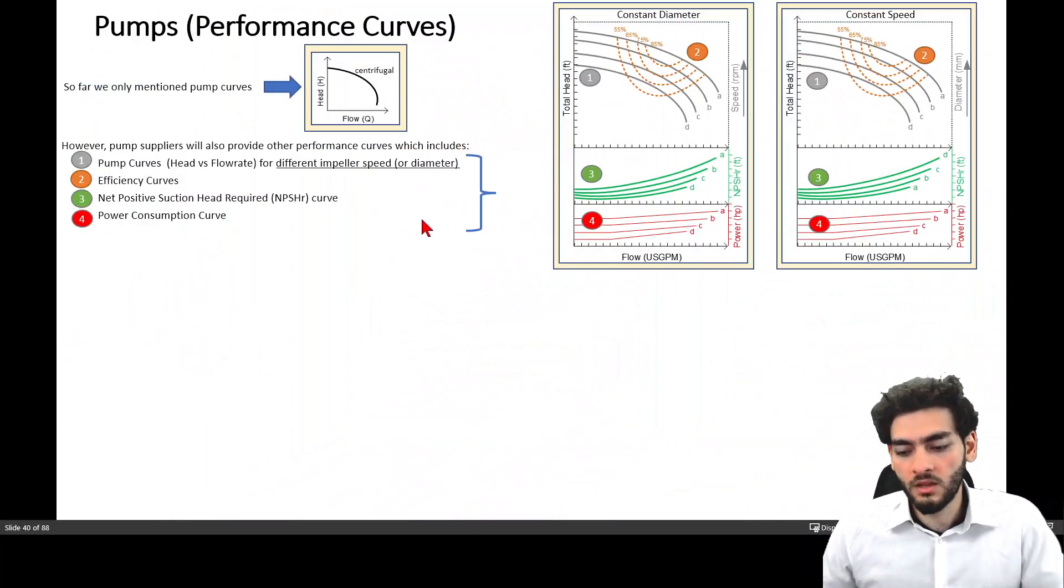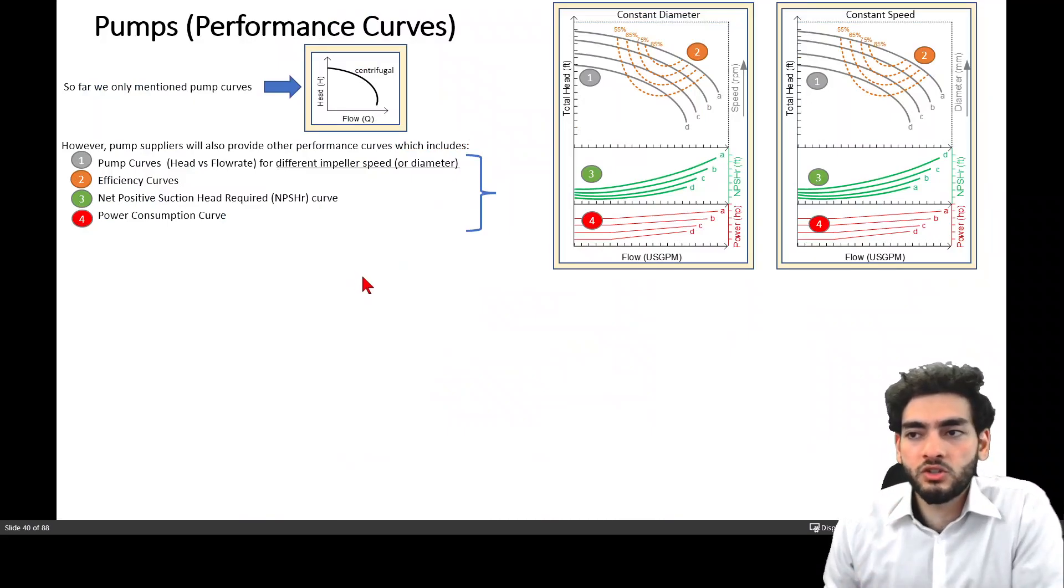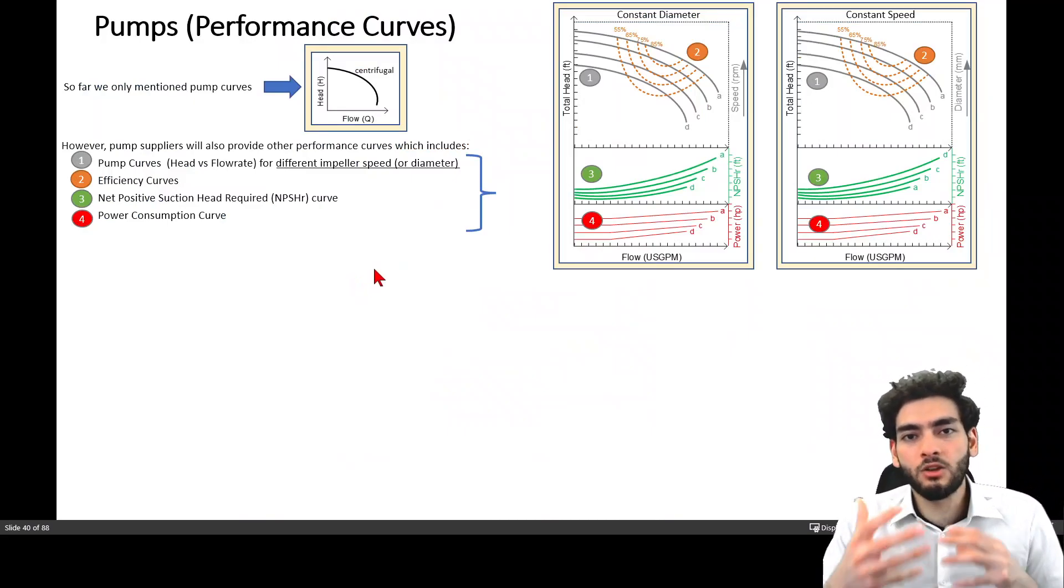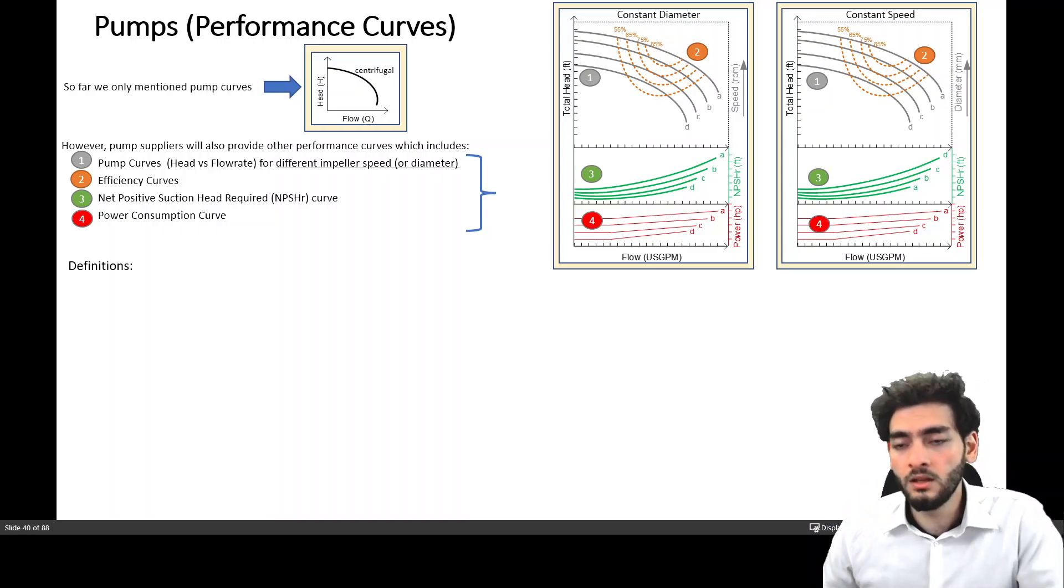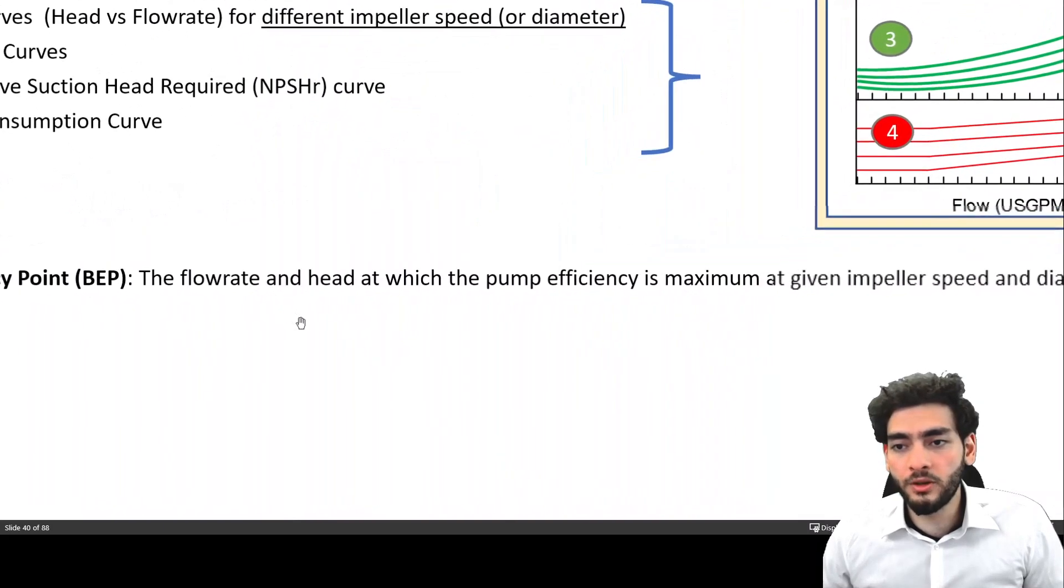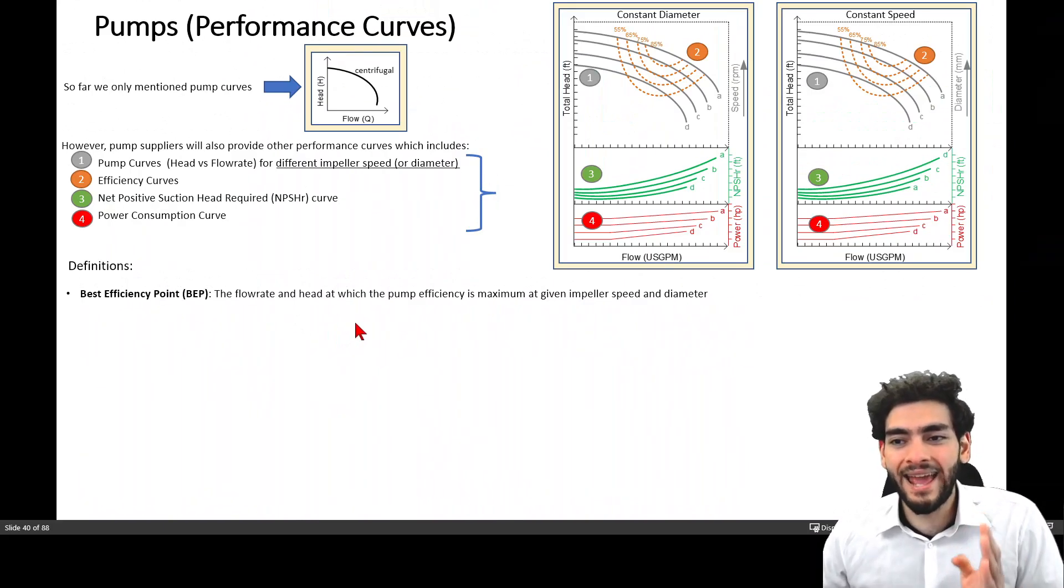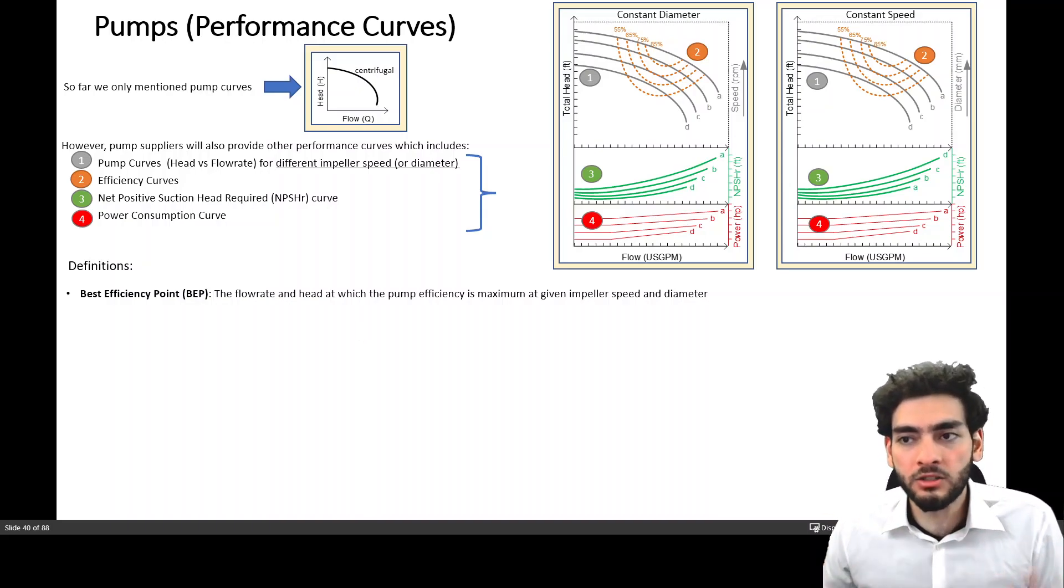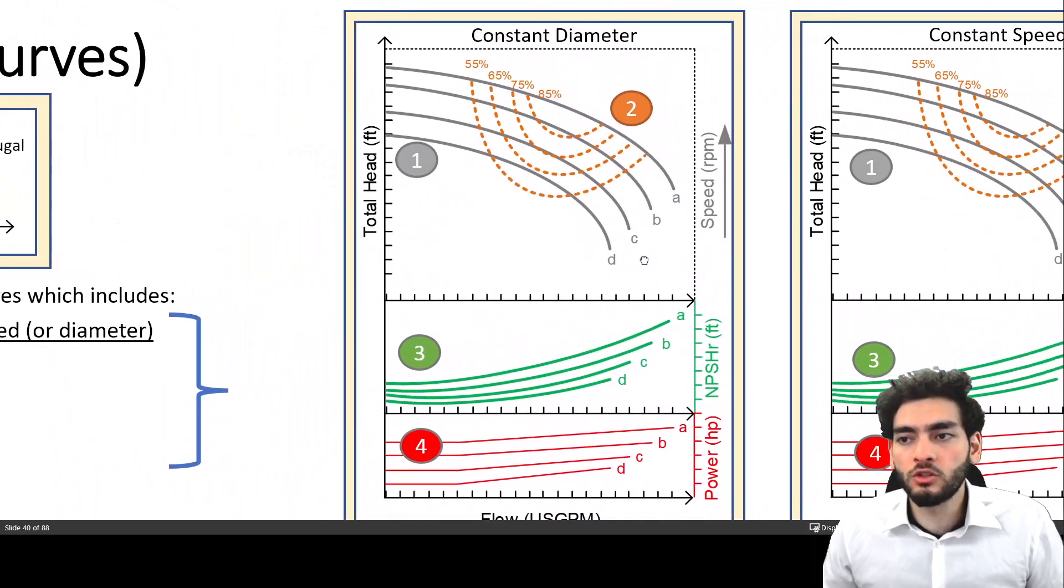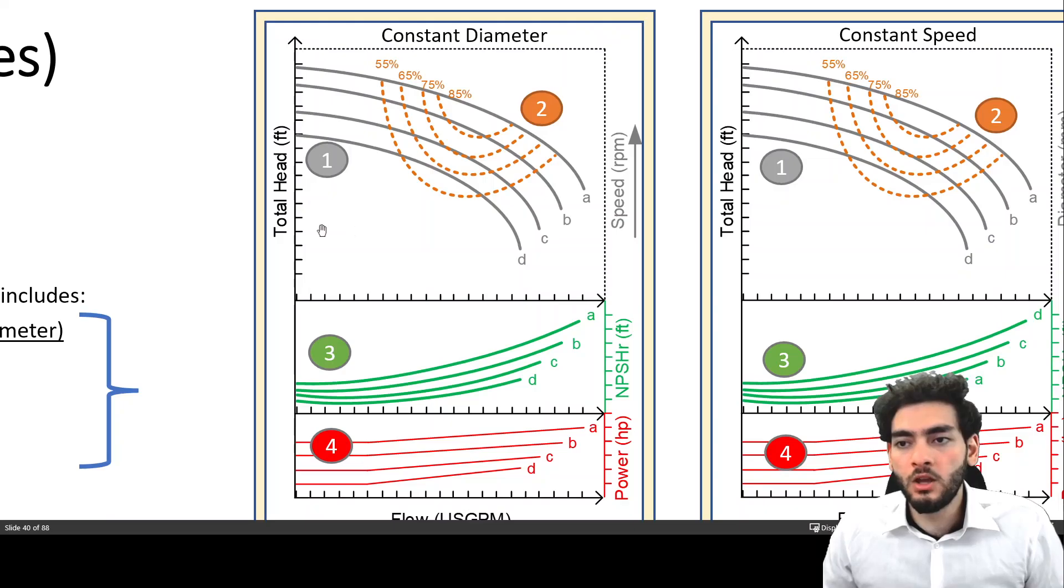Essentially, I want to go through some definitions with you because I've used best operating point and I haven't defined that. And there are some other terminologies that are important for you to know. So the best efficiency point is basically the flow rate and head at which the pump efficiency is maximum at a given impeller speed or diameter. So if we're looking at this curve, the best efficiency point would be operating closer to the 85% efficiency region.